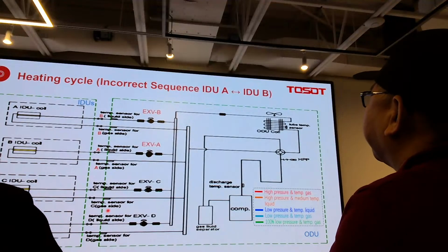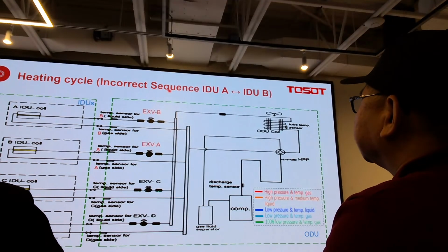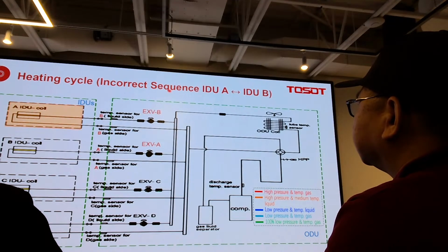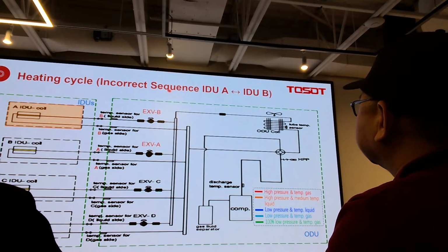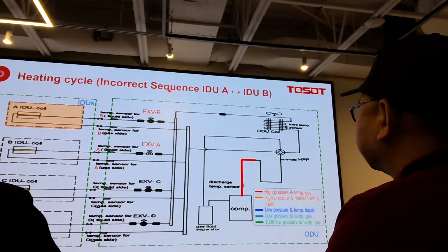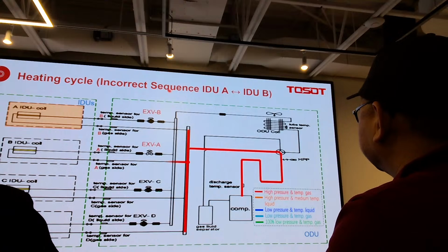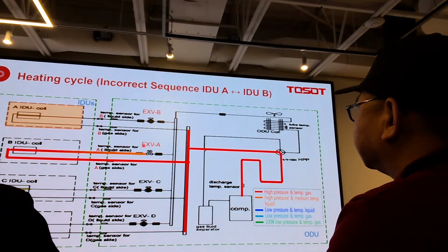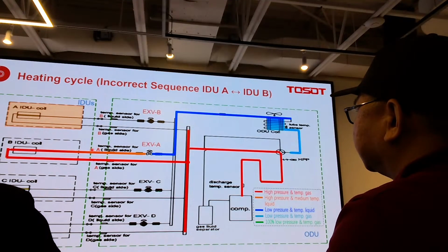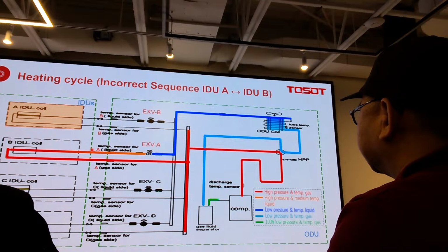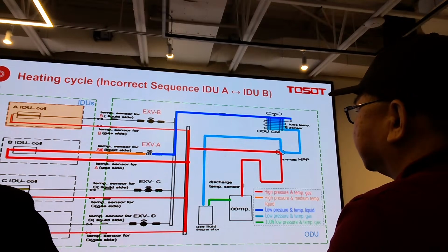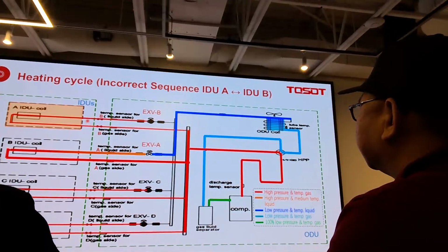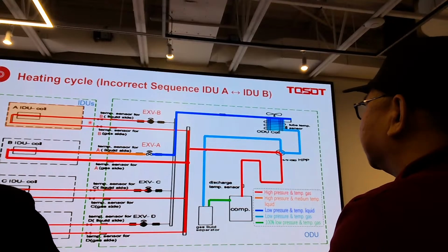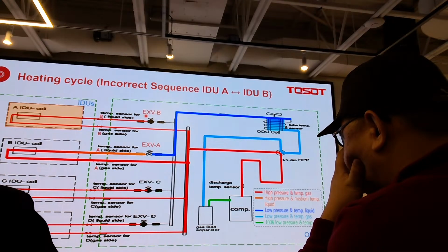So let's analyze if it's incorrect wiring. The sequence is incorrect. Also, zone A calls for heating. At this time, we just offer the hot gas to this one, and you can find it here, it's hot. But even if it's not for heating, we still open it a little bit for the refrigerant to flow through.